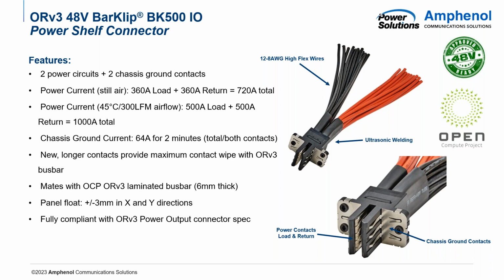This connector also features chassis ground contacts for 64 amps up to 2 minutes, very similar to the BK150. And we do not have sense contacts designed into this connector due to safety concerns, and something that we don't recommend doing given the high voltage and the high amperage within the connector system.